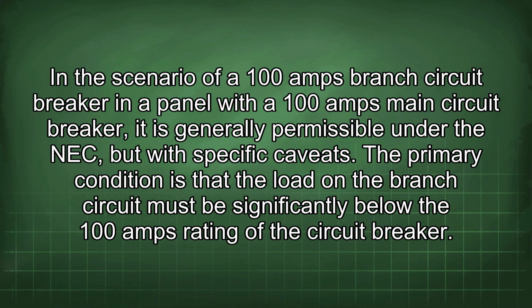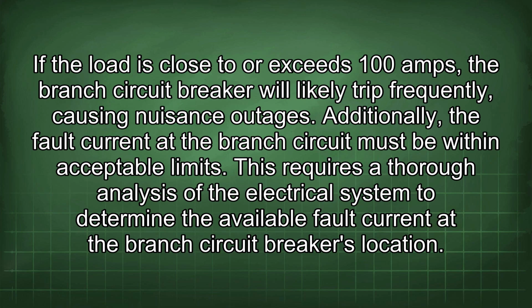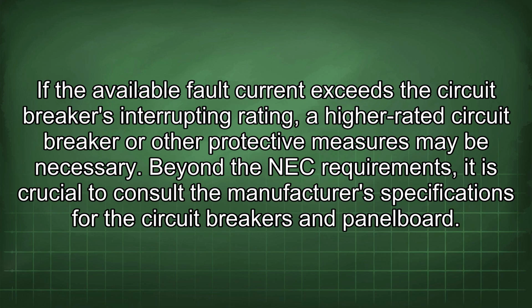In the scenario of a 100 amps branch circuit breaker and a panel with a 100 amps main circuit breaker, it is generally permissible under the NEC, but with specific caveats. The primary condition is that the load on the branch circuit must be significantly below the 100 amps rating of the circuit breaker. If the load is close to or exceeds 100 amps, the branch circuit breaker will likely trip frequently, causing nuisance outages. Additionally, the fault current at the branch circuit must be within acceptable limits. This requires a thorough analysis of the electrical system to determine the available fault current at the branch circuit breaker's location. If the available fault current exceeds the circuit breaker's interrupting rating, a higher rated circuit breaker or other protective measures may be necessary.